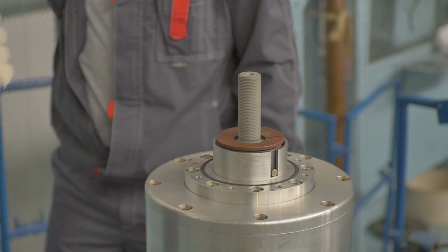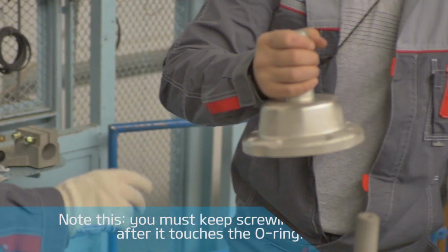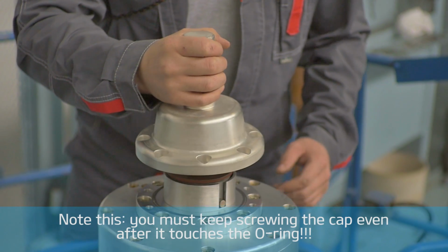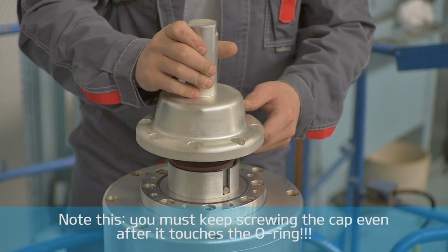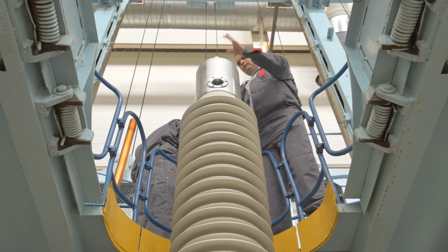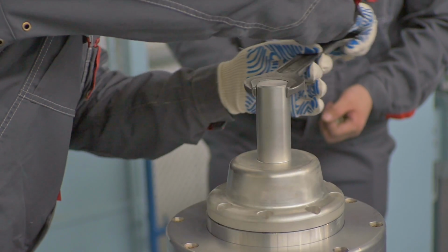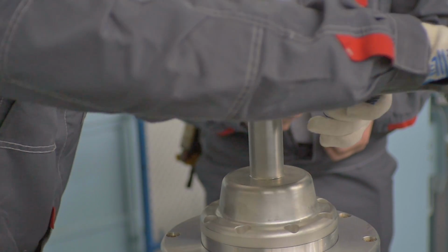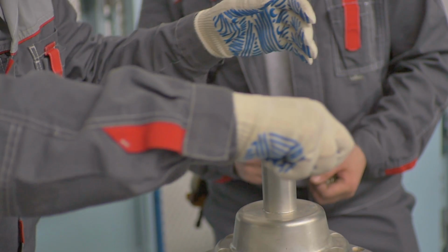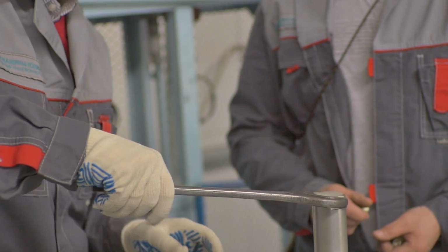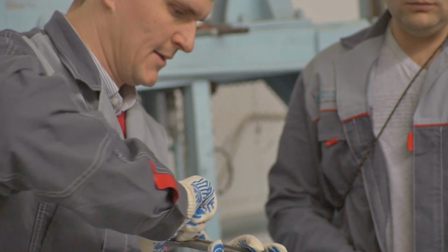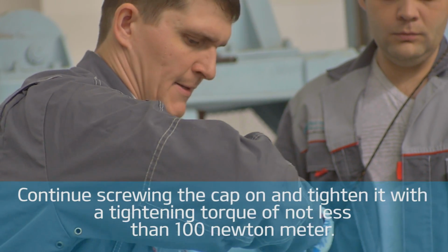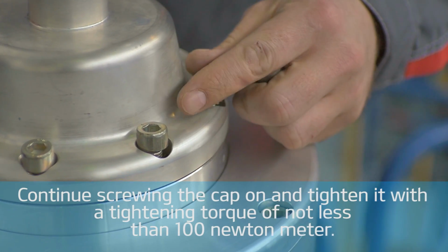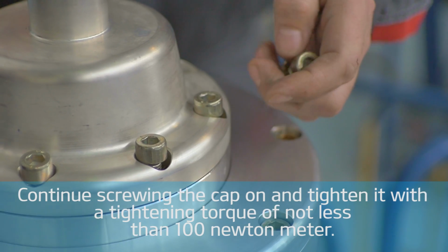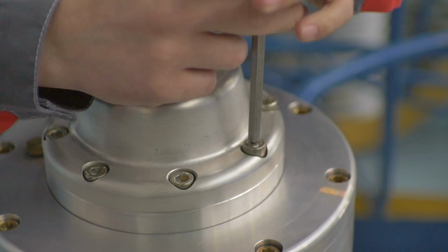Screw the brass cap onto the contact pin. Note, you must keep screwing the cap even after it touches the O-ring. If you bolt the cap to the bushing flange at this moment, later with the temperature change, the top side cap of the bushing will move by 2 or 3 mm, leading to a loss of air tightness. Therefore, continue screwing the cap on and tighten it with a tightening torque key of no less than 100 Nm.